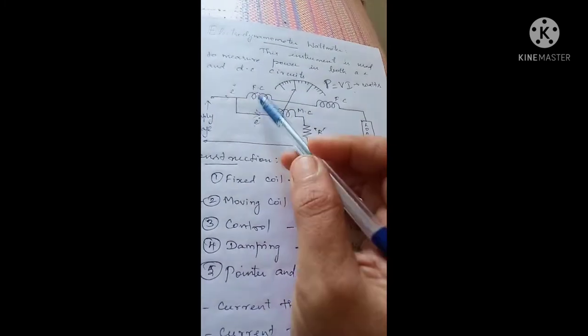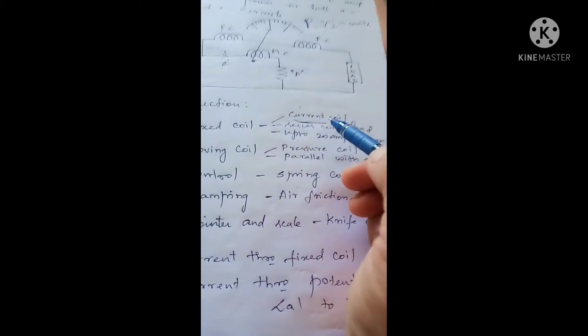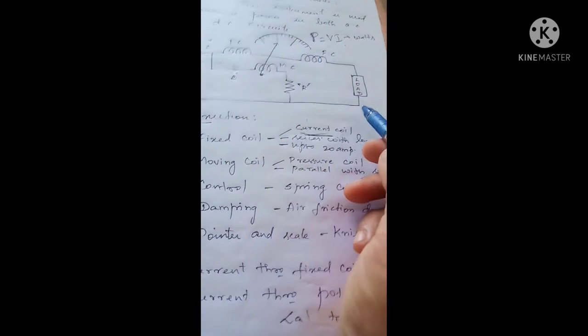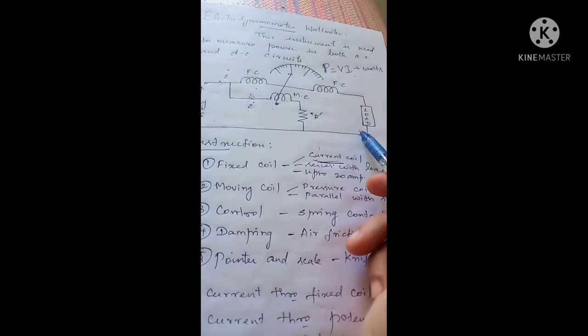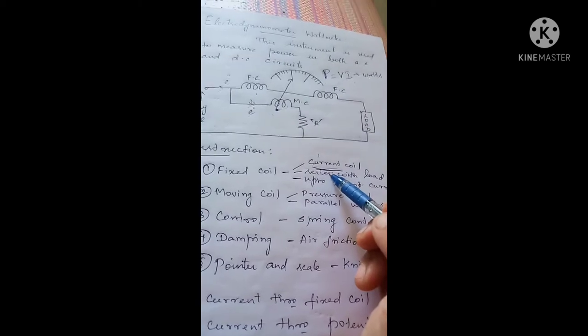The fixed coil is connected in series with the load, so it carries the load current — that's why it's also called the current coil. The moving coil is otherwise called the pressure coil, and it is connected in parallel with the supply voltage.